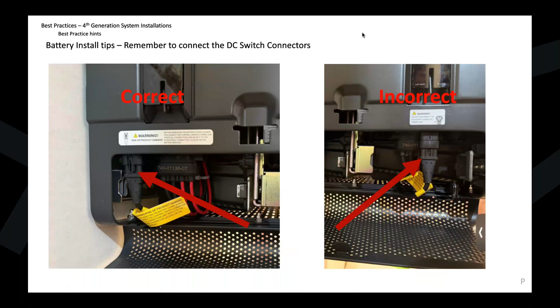On the right-hand side, that connector is flipped around, so the latch is on the back. When you slide that connector in, it won't latch or catch, and when you do your tug test, it just pulls out. So that's the incorrect way. We want to make sure that latch always faces outside, and when we secure that connector into the header and slide it up, make sure it clicks in and is secure.